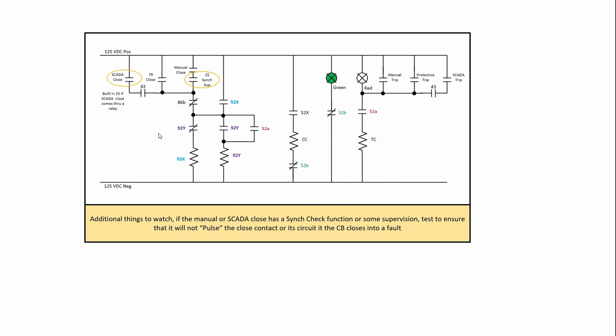In a similar fashion, the SCADA close and the manual close with a sync check and if the SCADA close has a sync check in it, you have to watch out for that. Sometimes I've seen it where we've had sync checks that would pulse if you close into a fault. They release the sync contact and again it defeats the anti-pump. So you have to be careful of that.